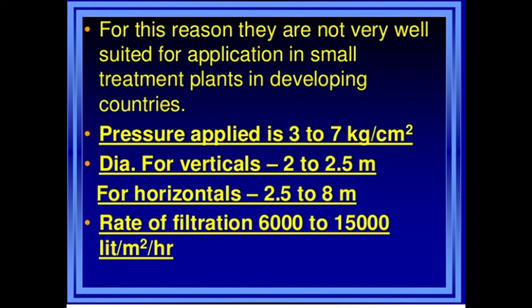Pressure filters operate at a pressure of about 3 to 7 kg per centimeter square. The diameter for vertical filters is about 2 to 2.5 meters, and for horizontal filters the diameter varies from 2.5 to 8 meters. They have a high rate of filtration of about 6,000 to 15,000 liters per meter square per hour.